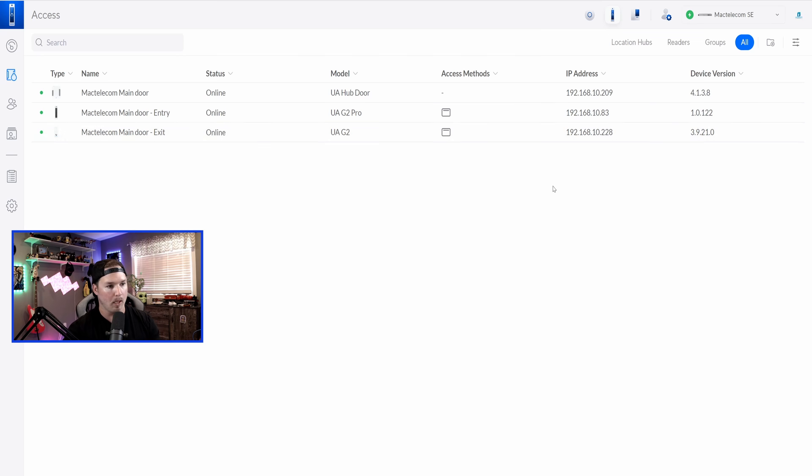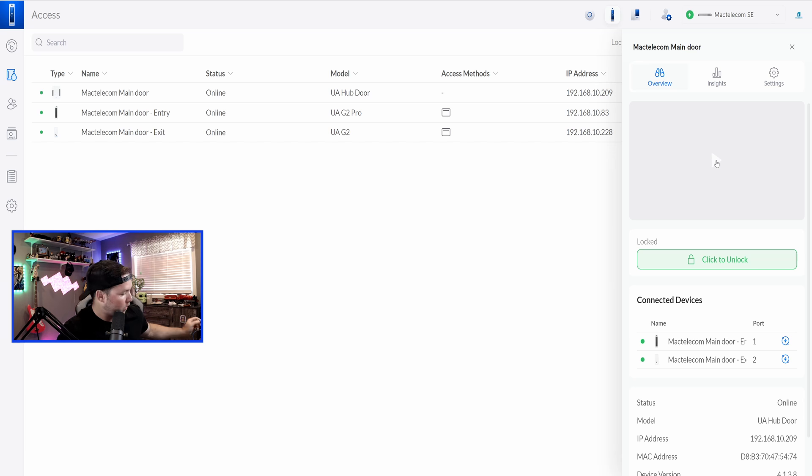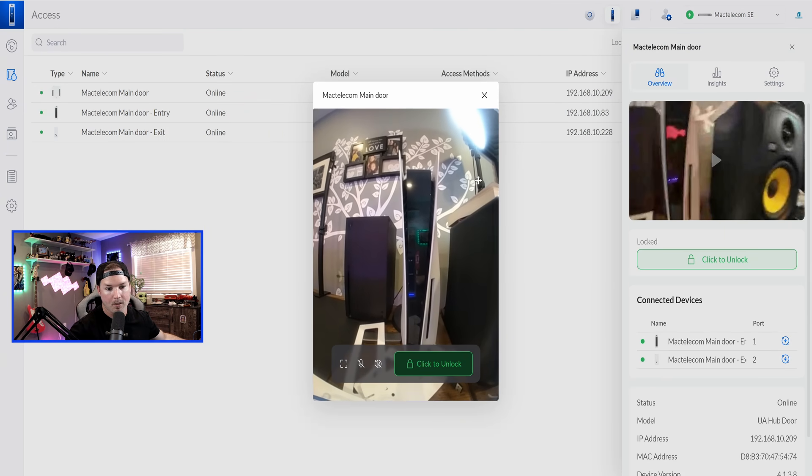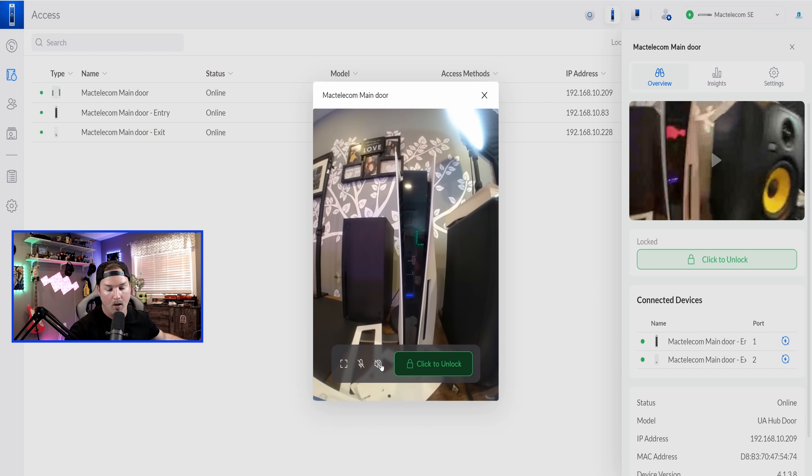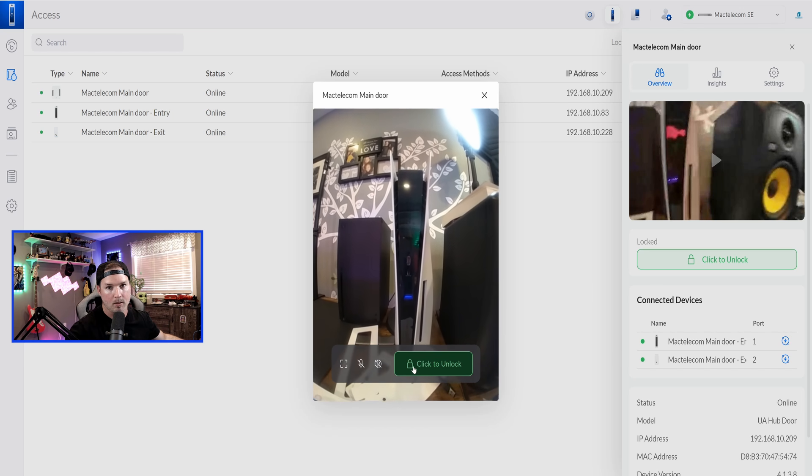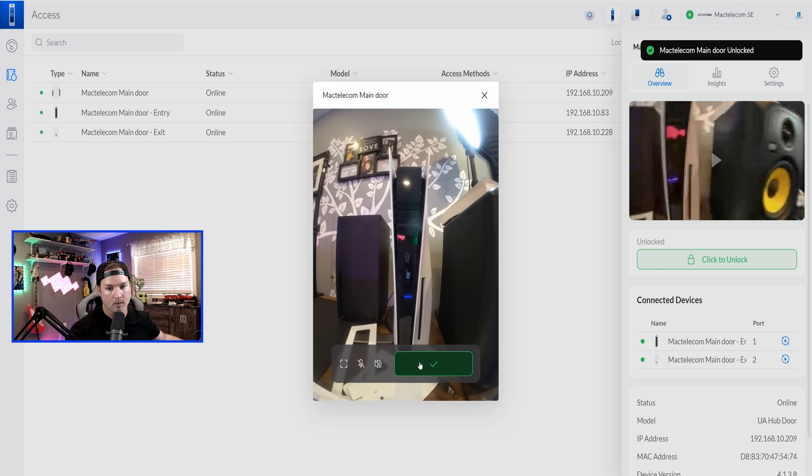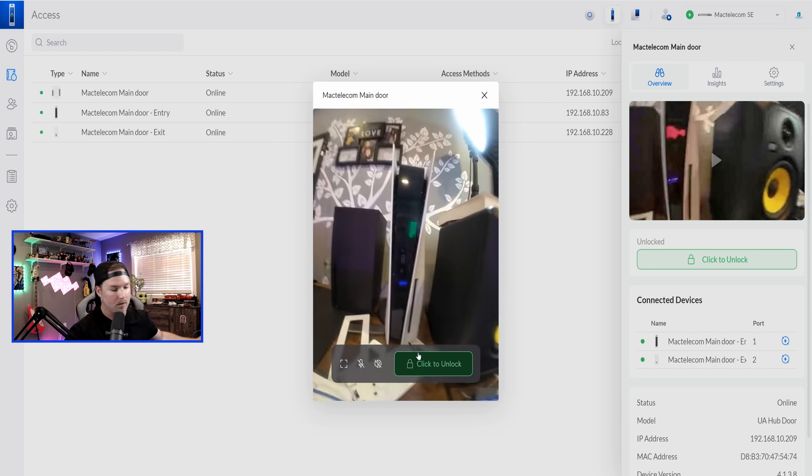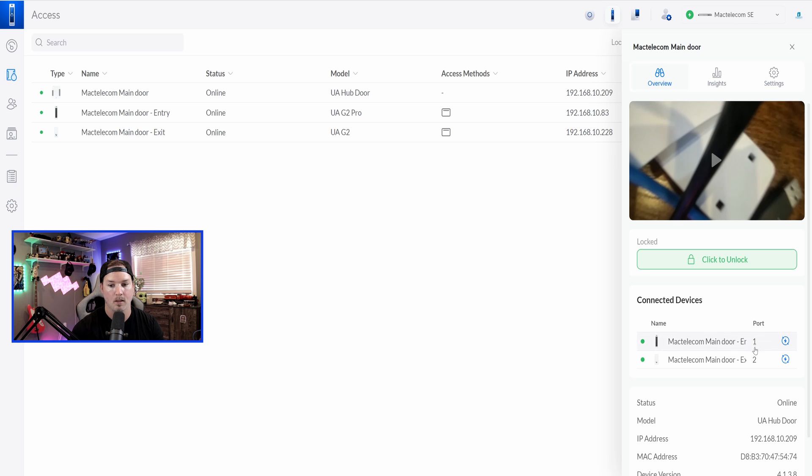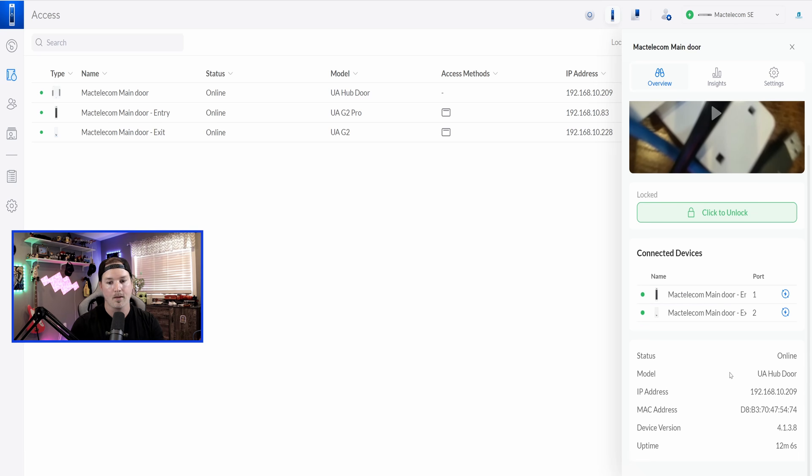Let's take a look one by one. This is the main door hub, and clicking on it, we could see the camera if we'd want it, and this is from the G2 professional reader. So I'll press play on that, and while I'm pressing play on that, you could see my PlayStation and my Xbox, and we could also unlock the door. We could unmute the audio, and we could use the microphone. I'm going to click to unlock. Now, it did make a sound, and I did hear the electric strike unlock. If we needed to, we could power cycle both of these readers directly from the access hub. On the right-hand side beside the reader, we could see the port number that it's plugged into, and then we could see the port power cycle. This is a great feature if for some reason your reader got hung.